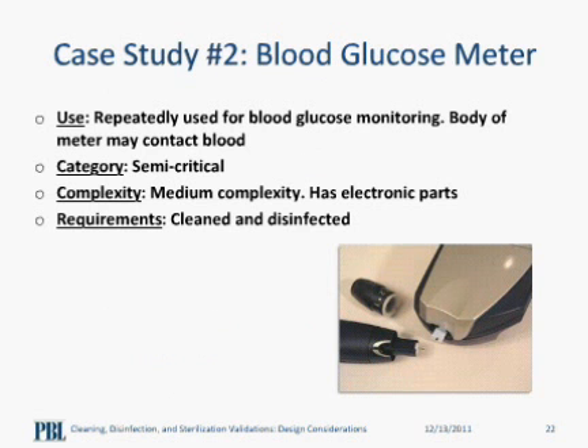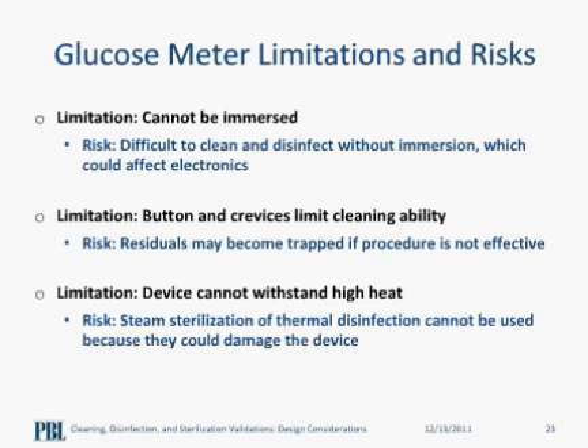Some of you may recall in our acceptance criteria summary, we said that semi-critical devices needed to be sterilized or disinfected. So why did we automatically choose disinfection over sterilization? Well, first of all, the glucose meter that we validated did not have sealed crevices or buttons, which meant that immersing this device in a cleaning solution would destroy the electronic components of the device. The buttons and crevices also pose a risk when cleaning because contaminants may become trapped in those areas. And we chose disinfection over sterilization because the electronic components will be destroyed by high heat or even thermal disinfection. And these devices also have plastic casings which will warp or even melt under high heat.